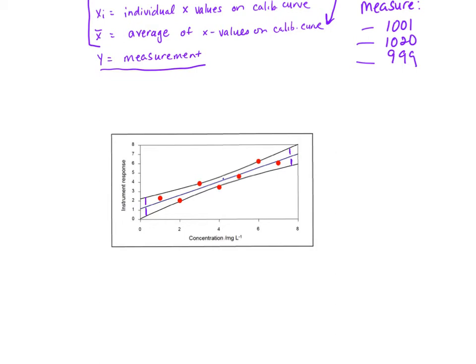Well, that doesn't actually account for the fact that the deviations get larger as you move away from the center point of the calibration curve. So here in this figure, which I have stolen from a really nice document that I found online, I'll find the reference for this for you and send it your way.